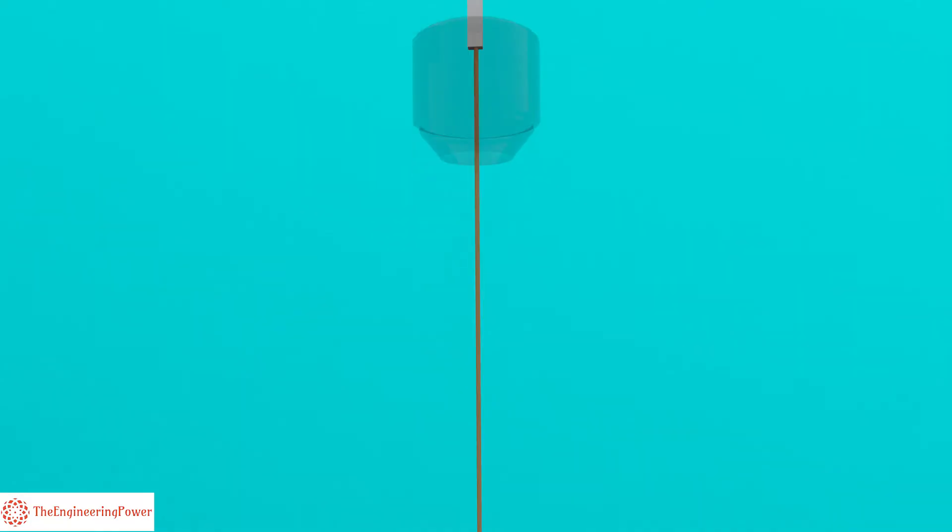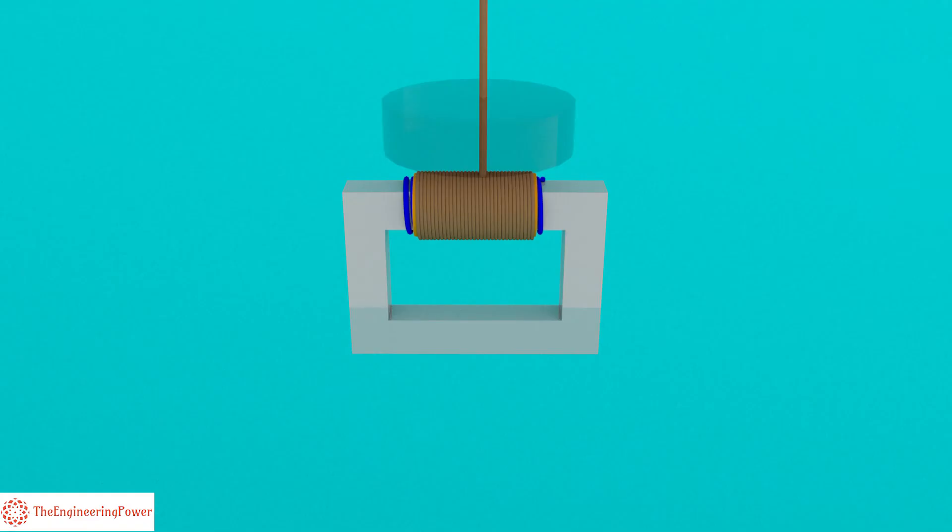The insulation helps to prevent any risk of short circuit between primary and secondary windings. The cable from HV terminal of PT is connected to one end of the primary winding. The other end of primary winding is connected to the neutral. Leads are fed from the LV winding to the secondary terminal box from where we take out necessary connections and get the output.